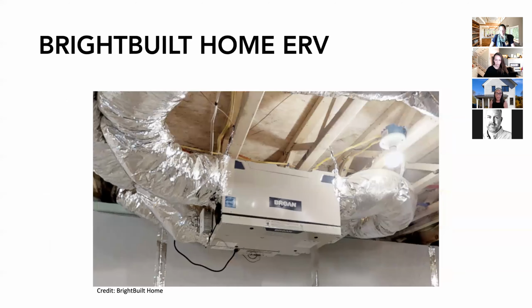Next slide, please. Thanks. Here is a BrightBuilt Home energy recovery ventilator. This is mounted to the ceiling of a basement. That is the exterior basement wall that you see with the silver lines of tape. The ducts are insulated. That's what you see up on the ceiling. The 2 on the right side, they're both going to the outside. Again, there's 2 grills on the outside of the home. One is taking in fresh air and one is expelling the stale air. And then on the left side of this unit, one is a supply for, again, the living room spaces, the bedrooms, and one is an extraction from the kitchen and bathrooms.